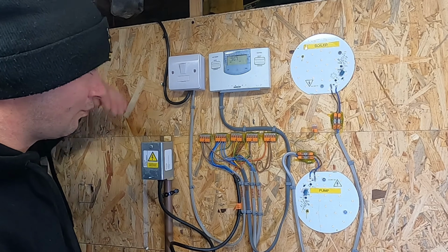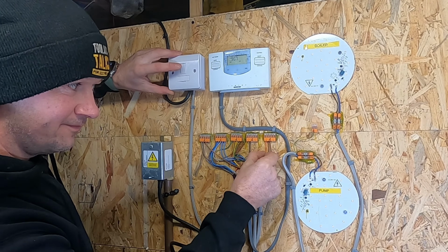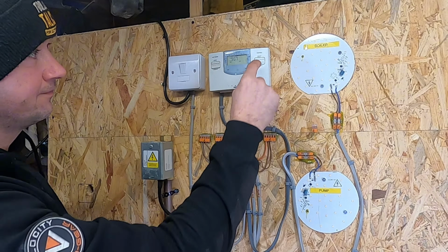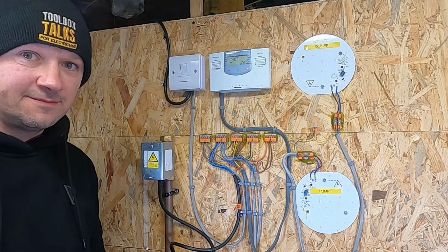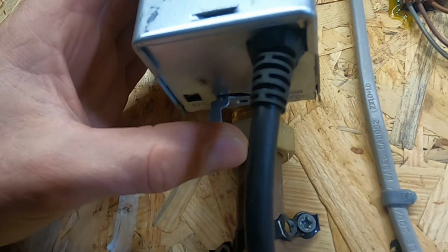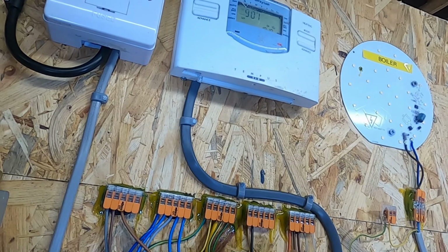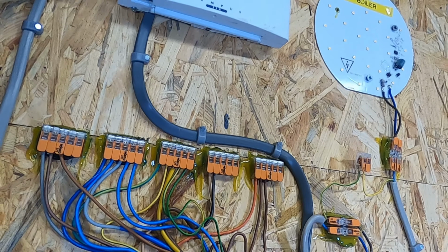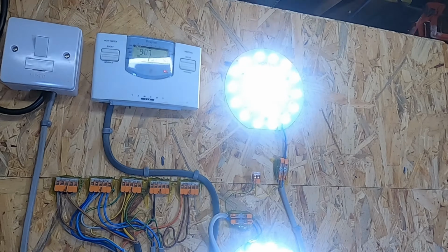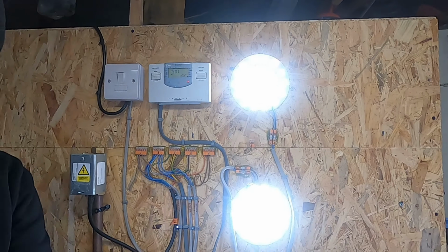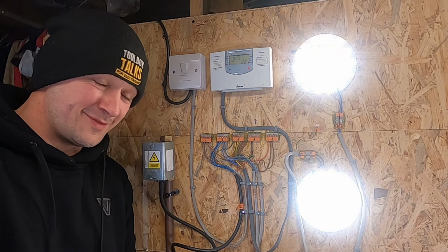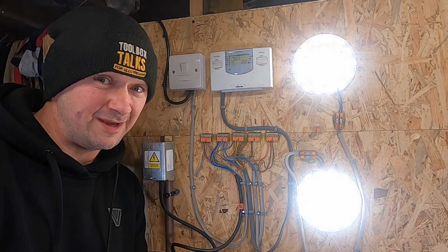So now, once the pump is in the right position, it was wrong before. Oh, so we turn it on and we boost it. The 2-port valve should open, yes, and then send the signal to the orange to say, yes, we're open. Let's get the boiler running and the pump running. There we go. So all them comments saying you've got that completely wrong, you are 100% right.